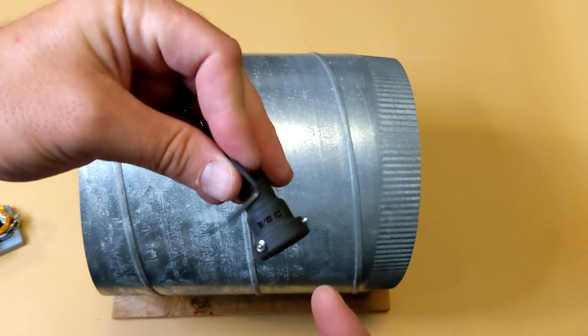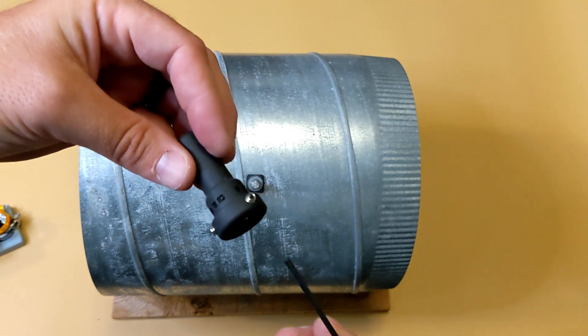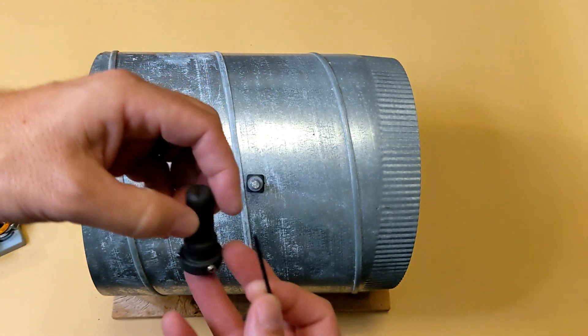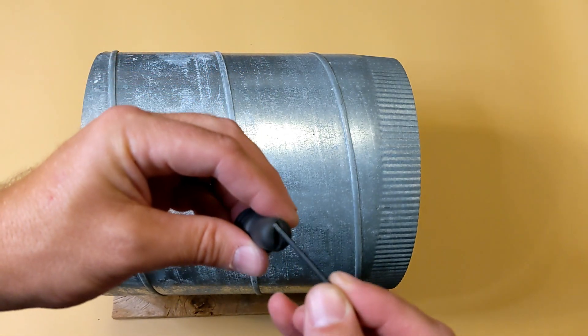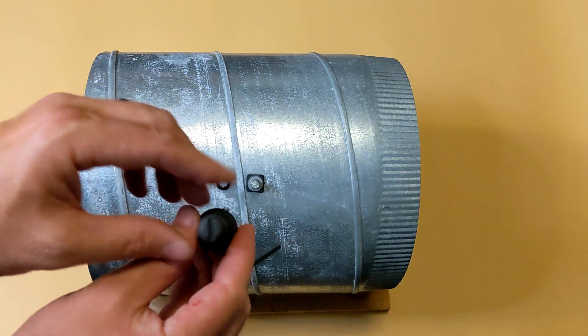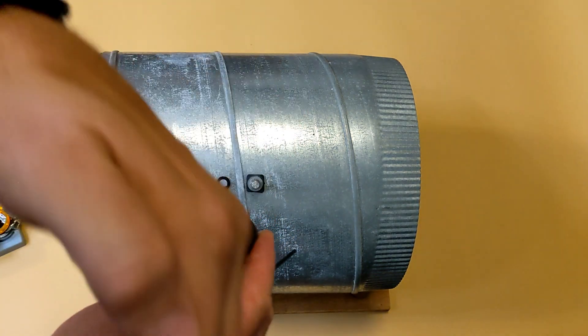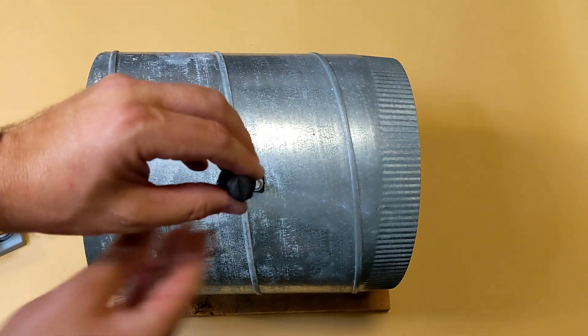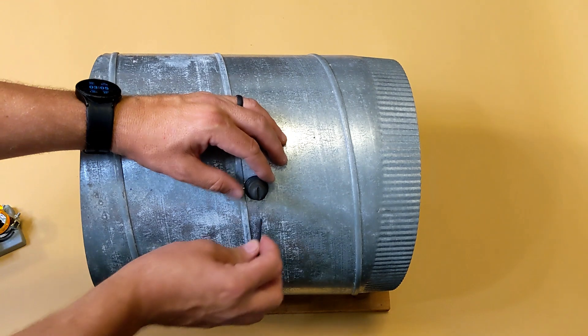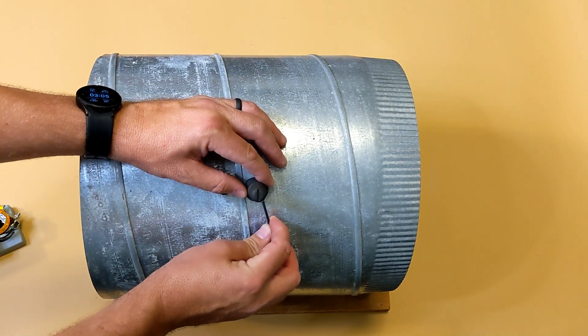This shaft adapter has three set screws that should be tightened evenly around the base of the shaft and a slot on the top of the shaft adapter that should be lined up with the blade inside the damper can. Now slip it down over the shaft all the way to the base and tighten the three set screws with the included hex key.